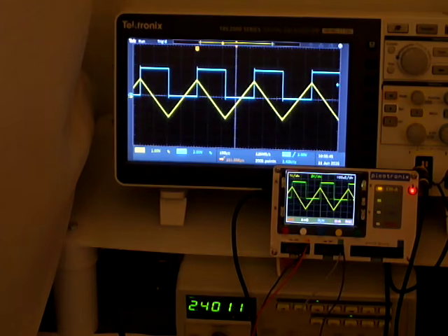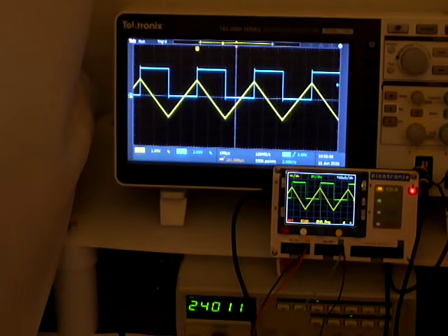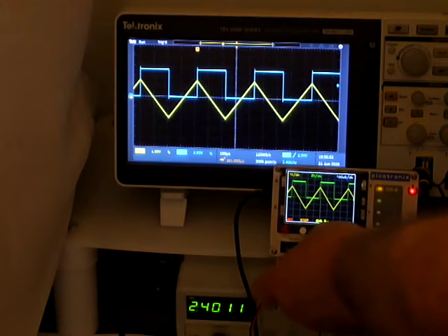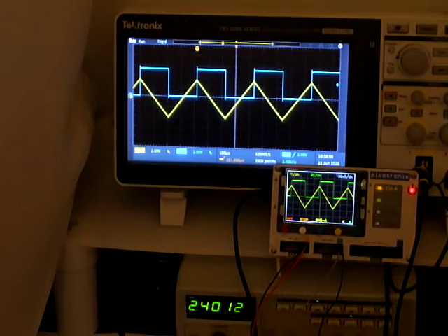So we'll go out of this mode now. So we're back to option one. Channel A range, we've changed that to 1 volt per division. And now what we'll do is we'll go on to channel B range. We'll leave that as it is. The next one is channel A ground.